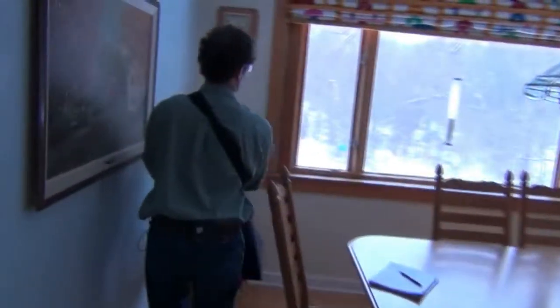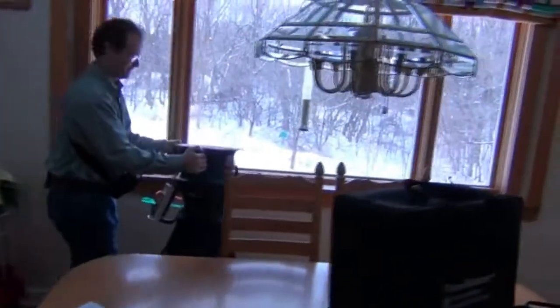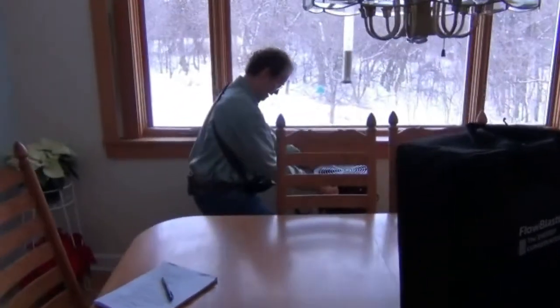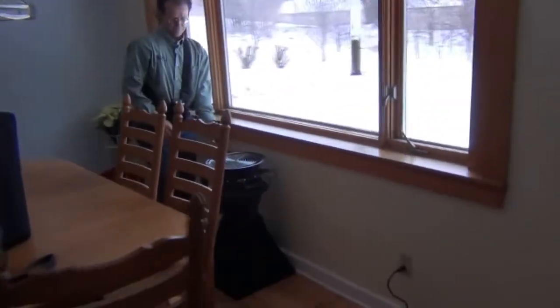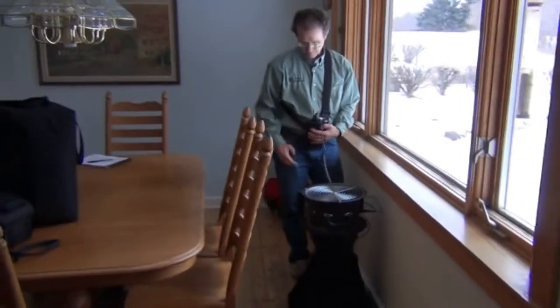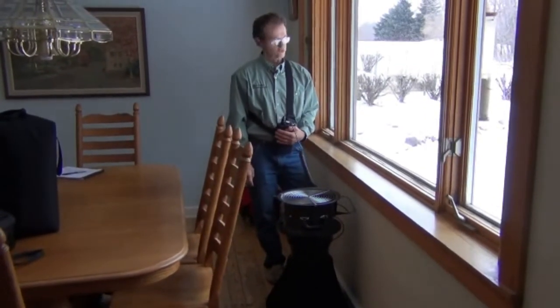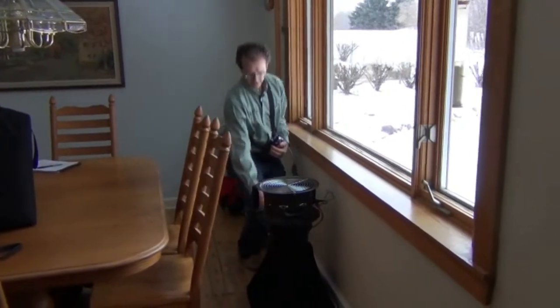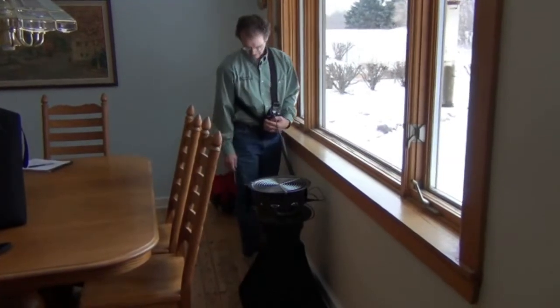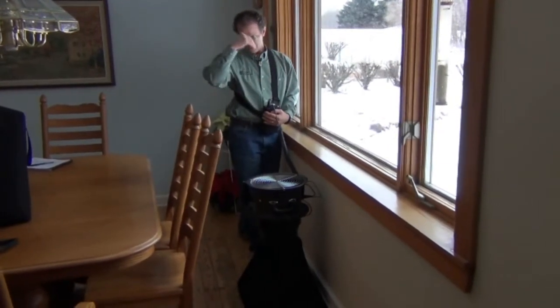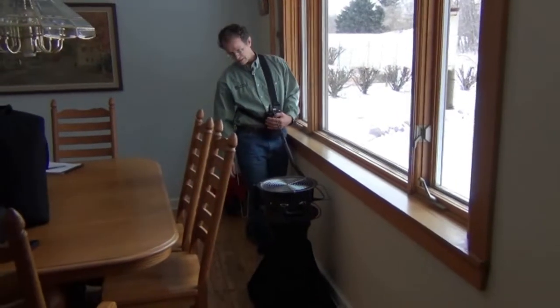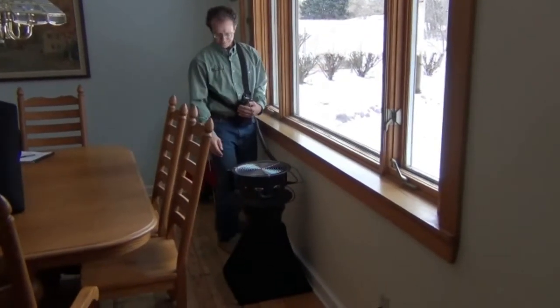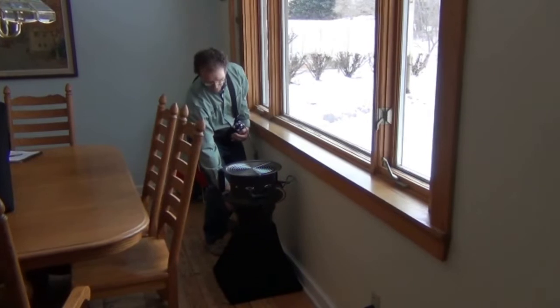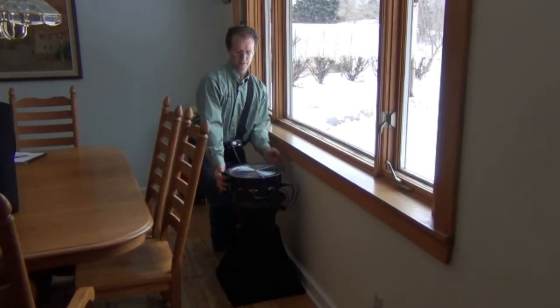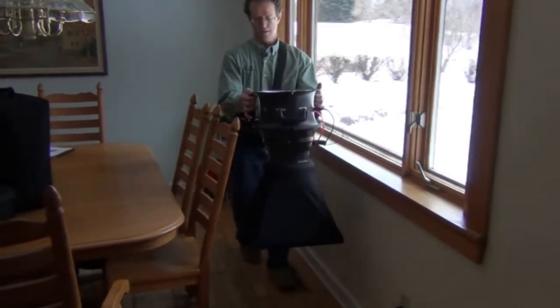Oh, it's starting to snow out. You can tell we're in Minnesota. I'll put it over the next register and we'll click start fan. This one will ramp up. Got a little bit more speed out of this one. And at this one, I'm watching the pressure. We're down to 0 and we're at 50 CFM. Now push stop fan. And we'll move to the next one.